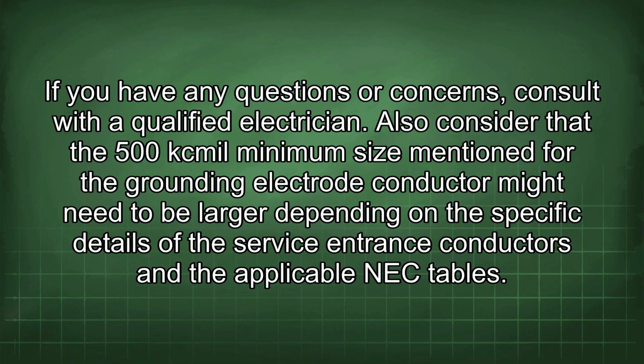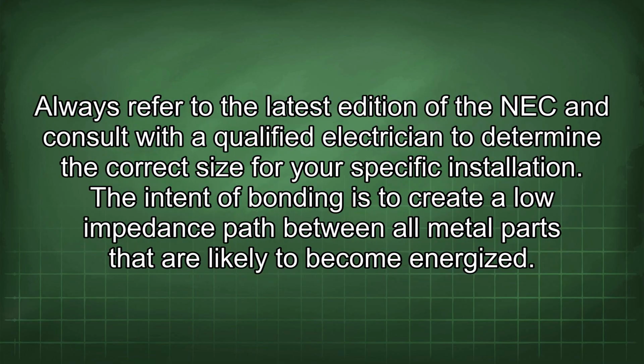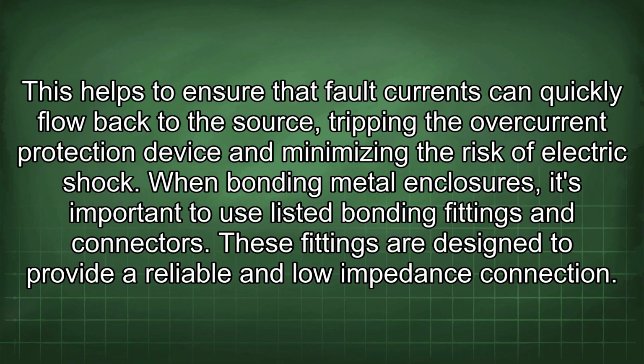Also consider that the 500 kcmil minimum size mentioned for the grounding electrode conductor might need to be larger depending on the specific details of the service entrance conductors and the applicable NEC tables. Always refer to the latest edition of the NEC and consult with a qualified electrician to determine the correct size for your specific installation. The intent of bonding is to create a low impedance path between all metal parts that are likely to become energized. This helps to ensure that fault currents can quickly flow back to the source, tripping the overcurrent protection device and minimizing the risk of electric shock.